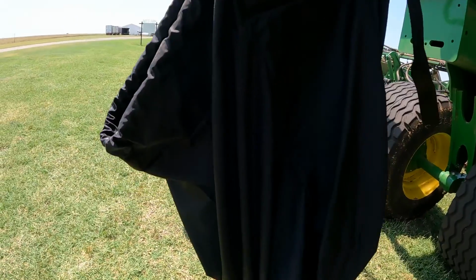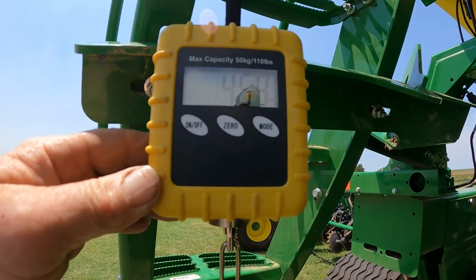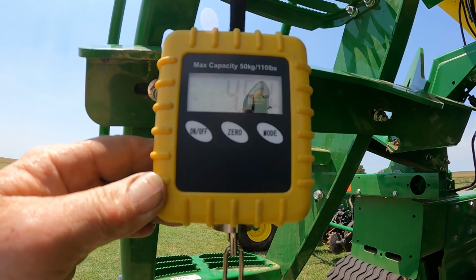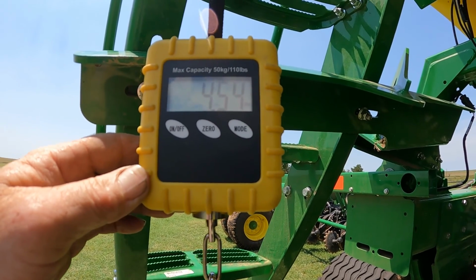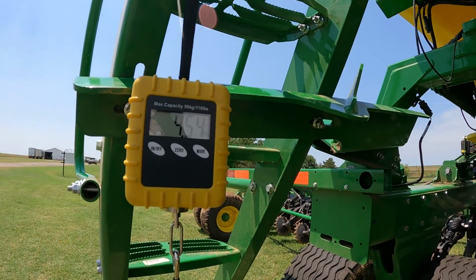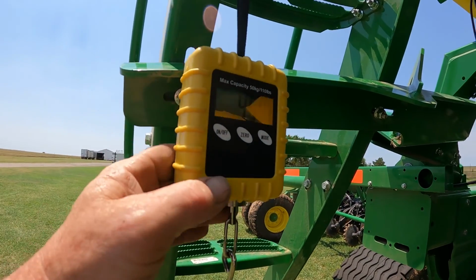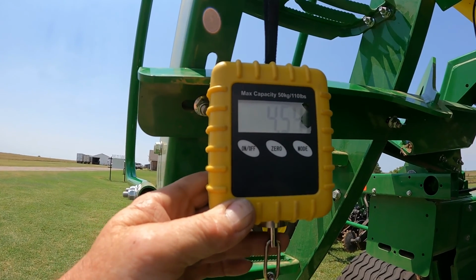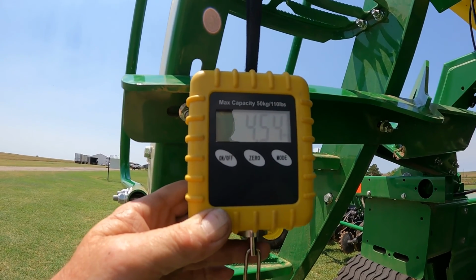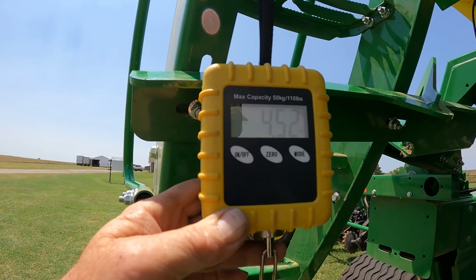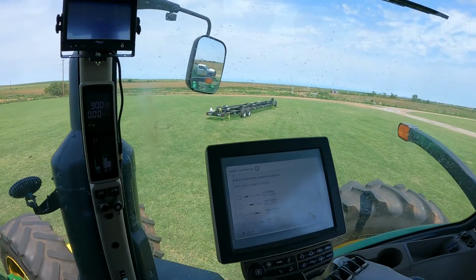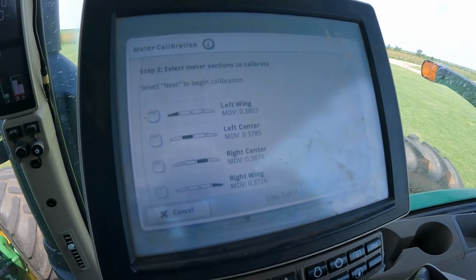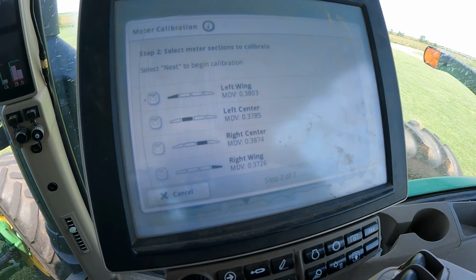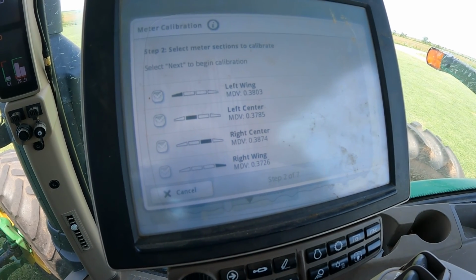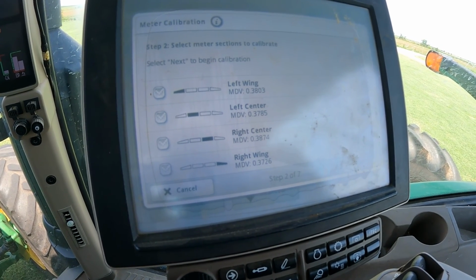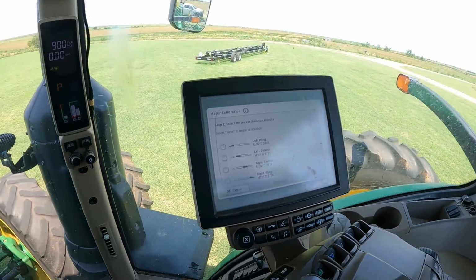So we've got our second bag here, our second collection sample, and it's 4.54. Our last was 4.56, so we're not very far off, which shows that we could take this cal number and put it in the rest of our meters and probably come out just fine. We got our calibration done on all 4 meters, and if you can see those numbers between left wing, left center, and right wing, the cal numbers are relatively the same. I'm pretty confident we got a good calibration on this.